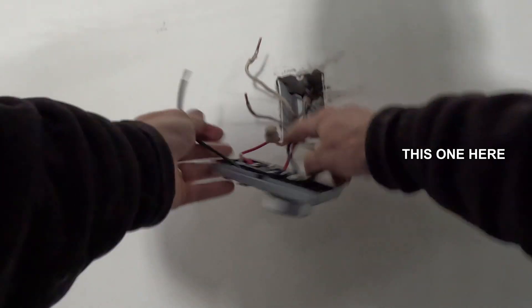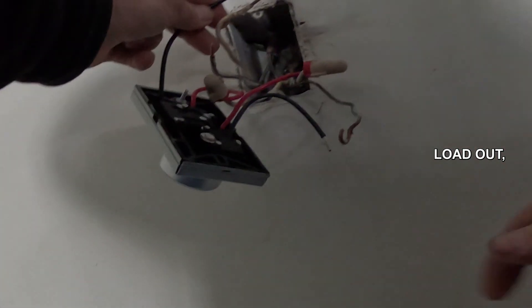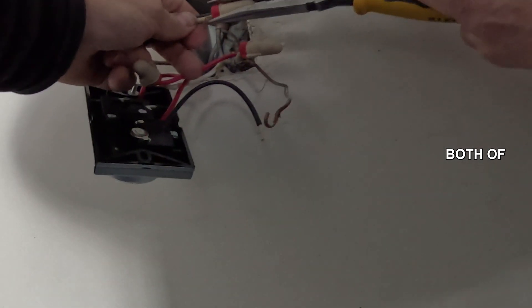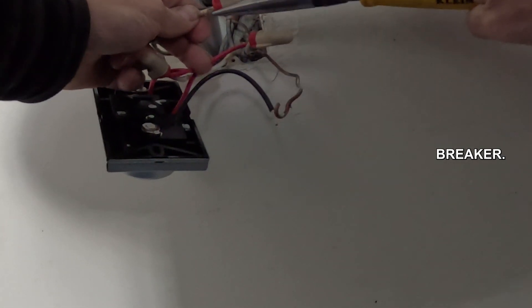And then this one here is your load, which you'll put with the other white here. This is my load out, which goes to my white going out to my heater. Like I mentioned before, this will just make sure when the thermostat's off it shuts off both of the circuits, both of the 110 on the breaker.